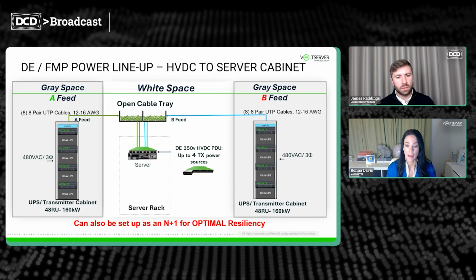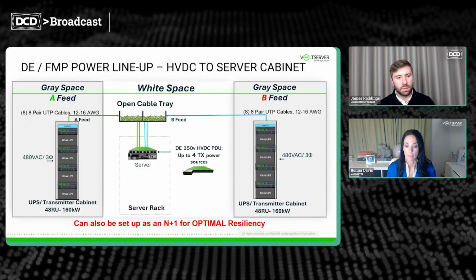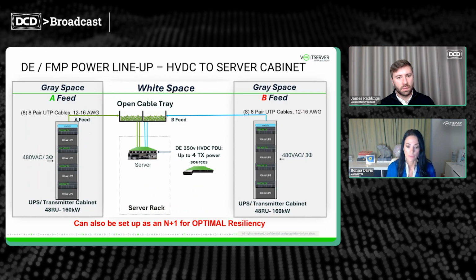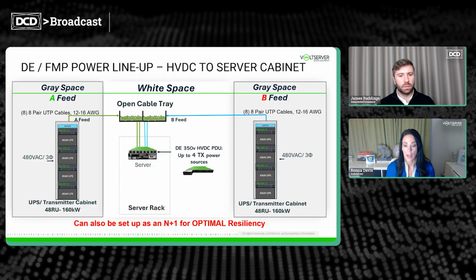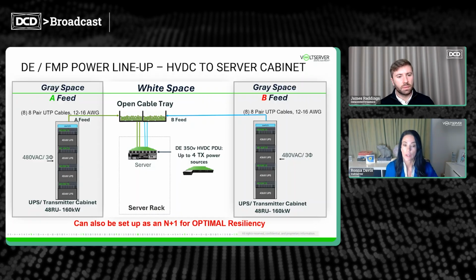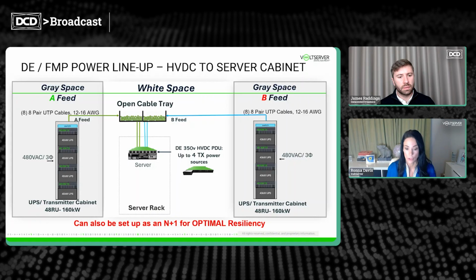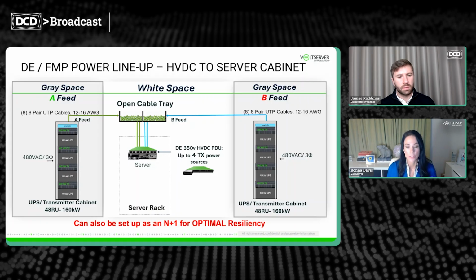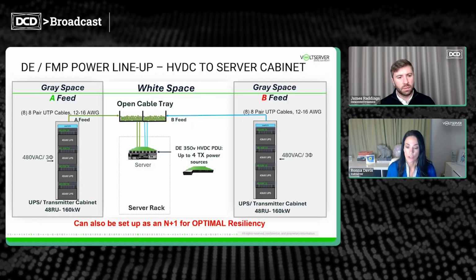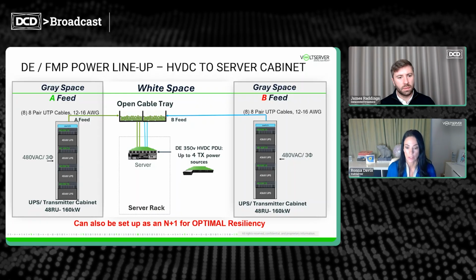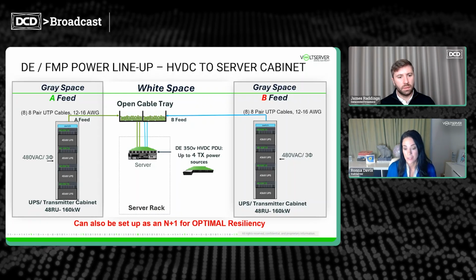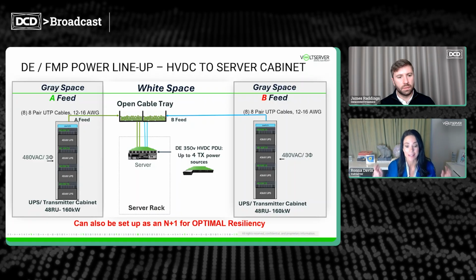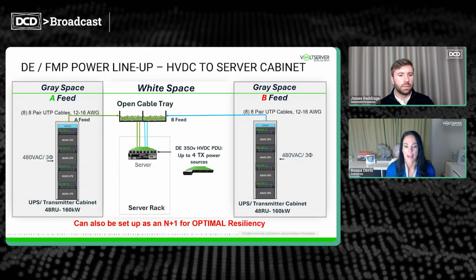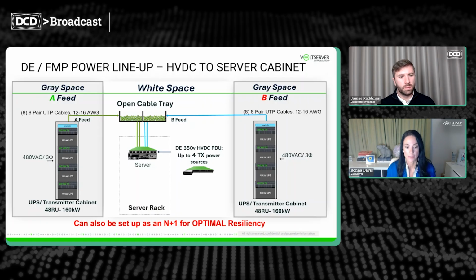That bundle runs in the basket tray to the server cabinets that are in the white space, where the UTP cables terminate to our high voltage DC PDU. The 350 volt high voltage DC PDU has 4 power sleds. Each can accommodate their own diverse power source. For this example, I am showing a 2N architecture, but our technology can use an optimal N+1 architecture for resiliency. Now, as you can see, digital electricity eliminates a lot of stuff in the data center, and the architecture is considerably simplified.